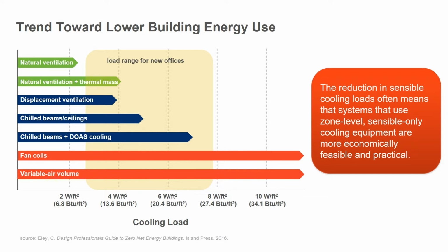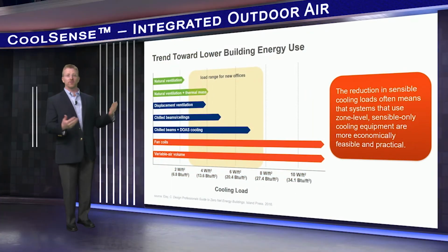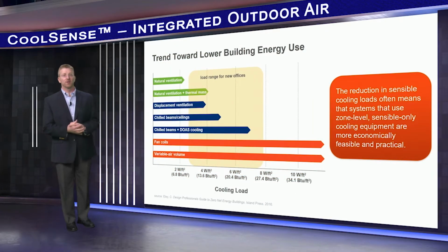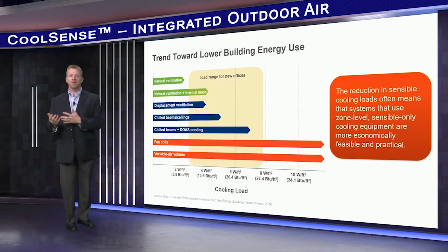Sensible cooling is not a new concept. In fact, some common examples include chilled beams, radiant cooling panels, radiant floors, and terminal units with sensible cooling only cooling coils, like CoolSense. The common characteristics of all of these devices is that they provide sensible cooling only. The latent loads are handled separately by a dedicated outdoor air system.